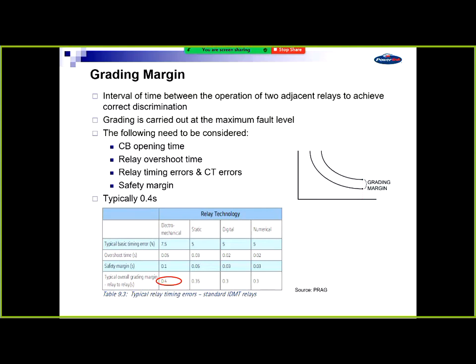This is what they say should typically, for different types of relays, be used. Practically speaking, everyone still uses that 400 milliseconds. So the 0.4 of a second is the sort of grading margin. It's been used for 40 or 50 years. It's good, it's safe. We don't trip spuriously on that. Why change? That's the sort of comment. You make it shorter and you're tripping incorrectly, you drop load off and people ask you, why did you do that? When there is no network concern, why do it? So typically we still use the 400 milliseconds, and that is just a good margin that is proven. It's good, safe, works well.